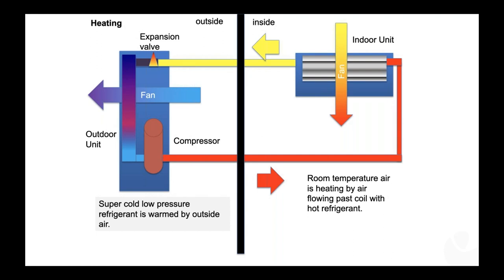And then when it goes into the compressor, it reduces the volume of the gas and compresses that heat energy into a smaller space. And the manifestation of heat energy in a tighter ball is a higher temperature. And so when the refrigerant comes out of the compressor, it now has that compressed heat energy. It's at 120 or even 130 degrees Fahrenheit. So then it travels along from the outdoor unit, from the compressor, into the indoor unit where it gets to the indoor coil. The indoor coil is heated up to 120 degrees or thereabouts, and the indoor fan draws air from the indoor temperature, 65, 68, 70 degrees, and goes through the hotter coil and picks off all that heat energy and flings it across the room to heat your sofa and sheetrock and your cat. And the cycle continues.